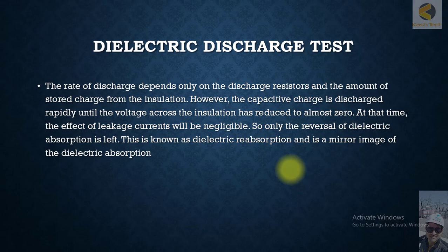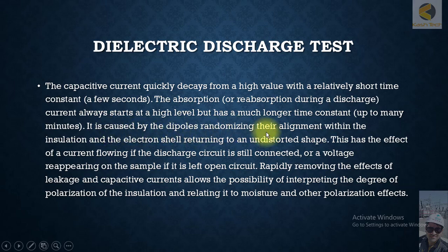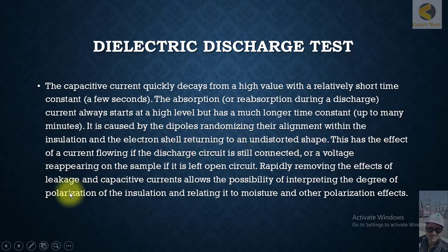The capacitive current quickly decays from a high value with a relatively short time constant of a few seconds. The absorption or reabsorption during discharge current always starts at a high level but has a much longer time — up to many minutes. It is caused by dipoles randomizing their alignment within the insulation and electron shells returning to an undistorted shape. This has the effect of current flowing if the discharge circuit is still connected, or voltage reappearing on the sample if it is left open circuit.